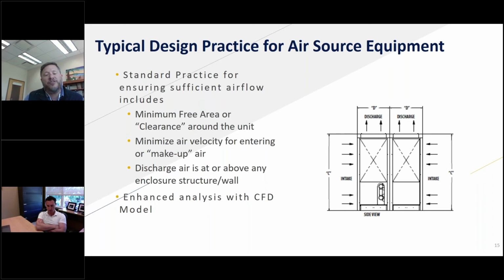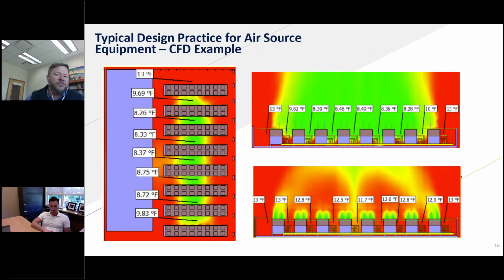And there are ways of doing that, short of and including a CFD analysis. When we do a CFD model, we're looking at the airflow requirements. We're looking at things like prevailing winds. We're looking at lots of different factors, and we're computing what we believe the entering air temperature is going to become if there's going to be some air recirculation, okay? Where that becomes even more important is not in a single unit application most times. It's if we're going to have lots of units all stacked together on the same roof. And so I've got some examples of what that looks like.